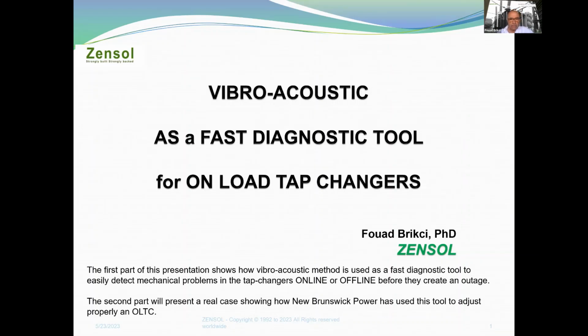So the first part of this presentation shows how the Vibro-Acoustic method is used as a fast diagnostic tool to easily detect mechanical problems in the tap changers, online or offline, before they create an outage. The second part will present a real case showing how New Brunswick Power has used this tool to properly adjust an OLTC.